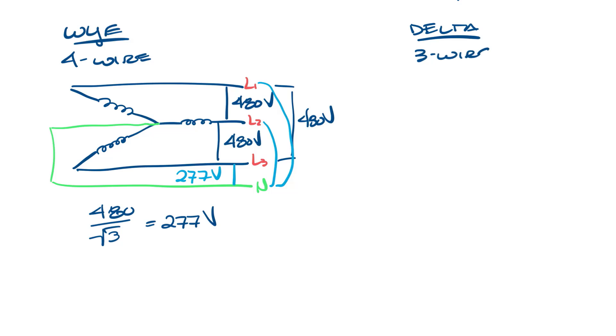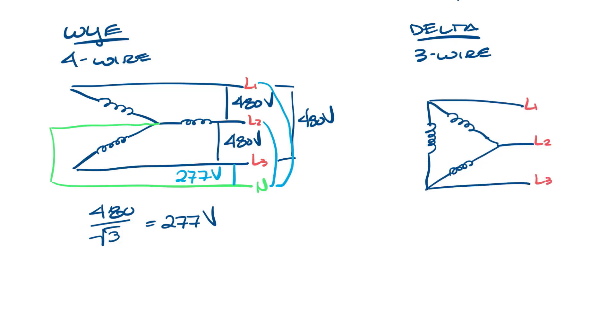Now let's look at the three-wire Delta. It looks like a Delta symbol. There are only three wires, so you have L1, L2, and L3. With the three-wire Delta, you only get full voltage, or 480 volts, line to line. So between here, here, here, and here, are all 480 volts.